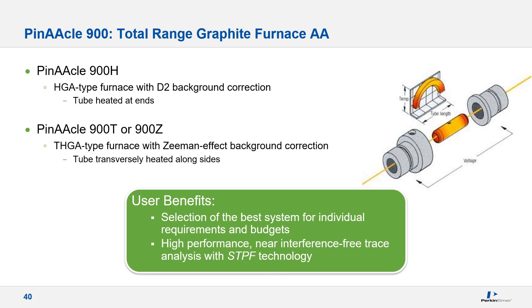The PinAAcle 900H is equipped with a Massman-type longitudinally heated graphite furnace with deuterium background correction. The 900T and 900Z are equipped with a transversely heated graphite furnace with longitudinal Zeeman effect background correction, allowing the user to choose the system that best meets requirements and budget. For example, if the only graphite furnace need is lead in drinking water, the 900H would be acceptable given the simple matrix. However, for more complex matrices such as wastewater or sludge, the 900T or Z with Zeeman correction would be the best choice, as it can accurately correct for higher levels and structured background. Both systems use graphite tubes with integrated platforms for stabilized platform furnace technology, providing near interference-free analyses.